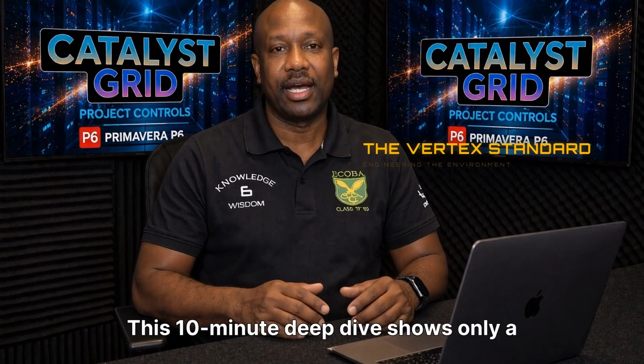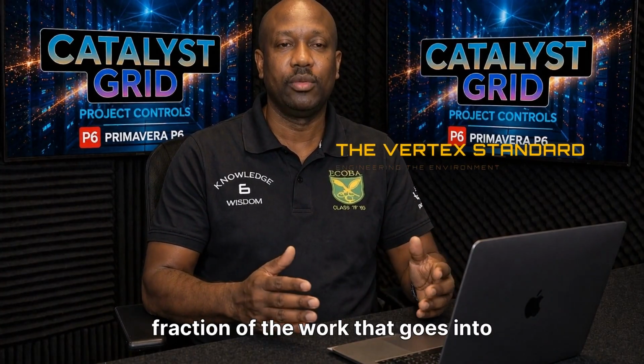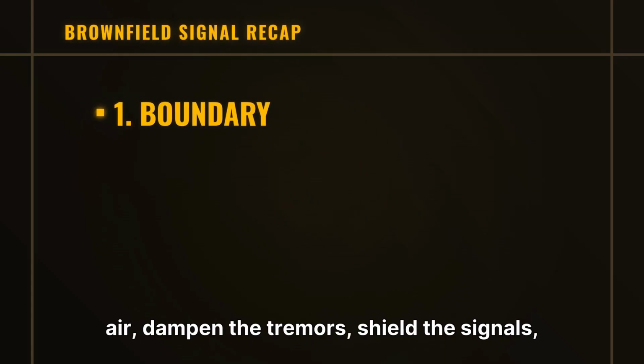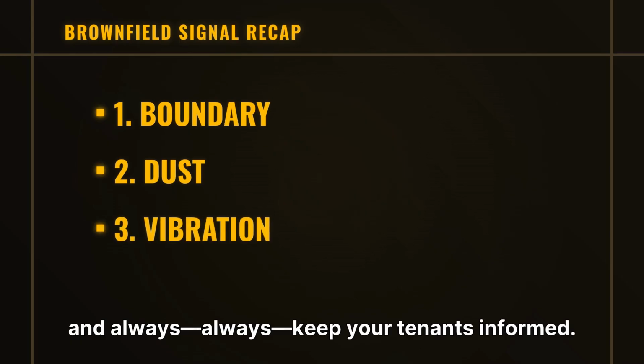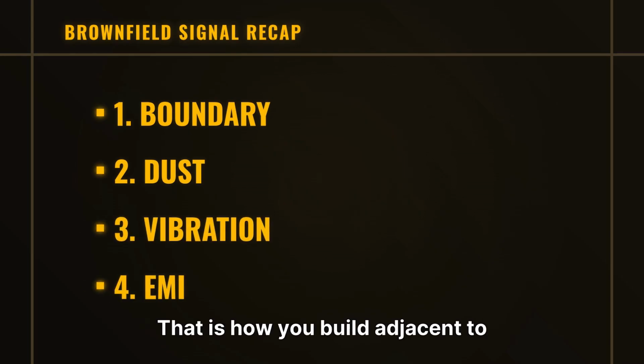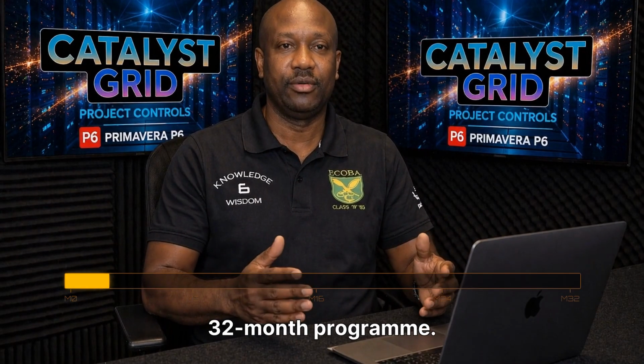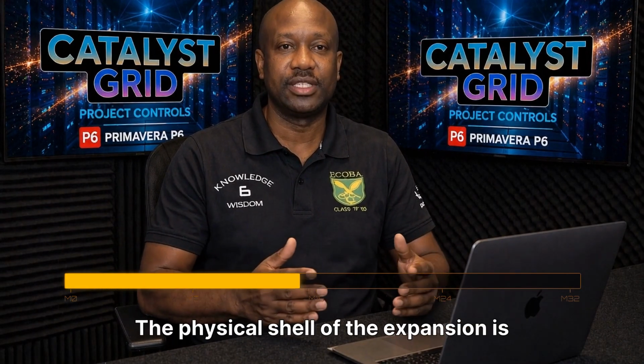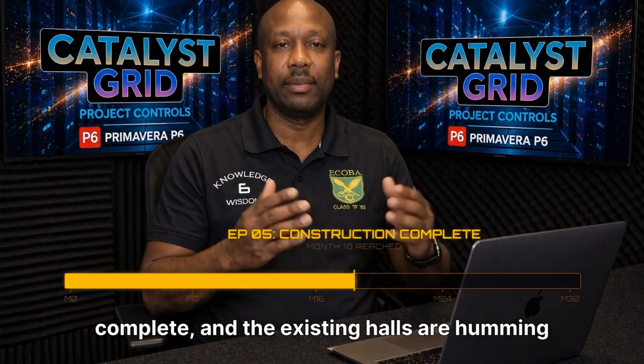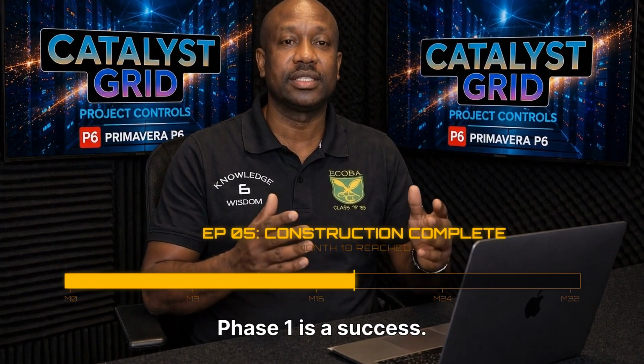This 10-minute deep dive shows only a fraction of the work that goes into protecting the live load. To recap, isolate the boundary, scrub the air, dampen the tremors, shield the signals, and always keep your tenants informed. That is how you build adjacent to live IT. We have reached month 18 of the 32-month program. The physical shell of the expansion is complete, and the existing halls are humming along perfectly. Phase 1 is a success.